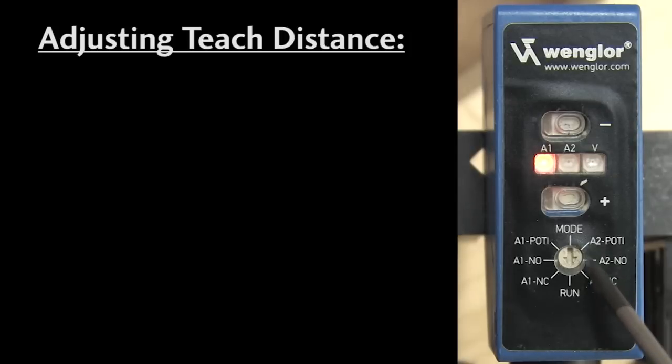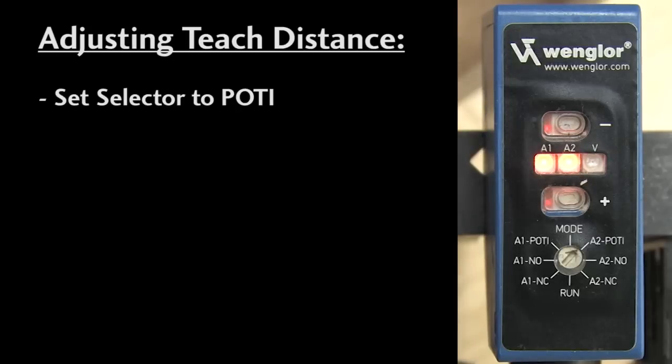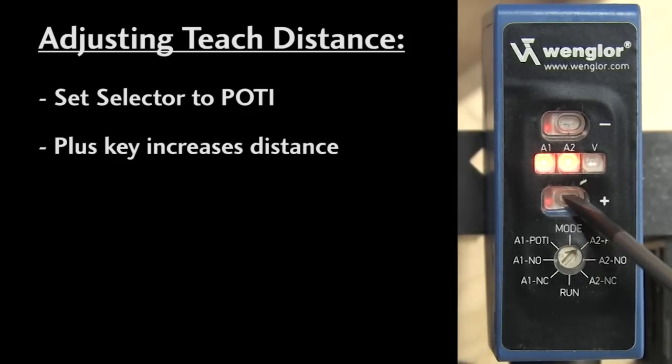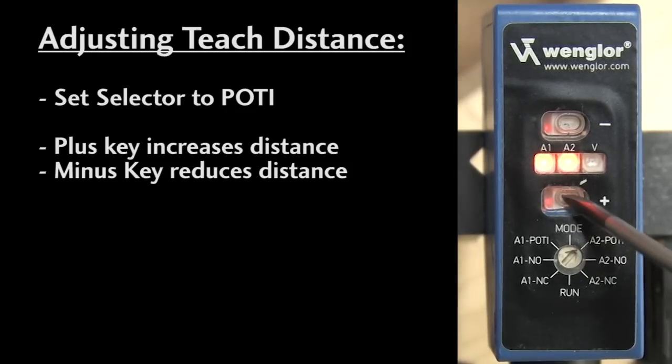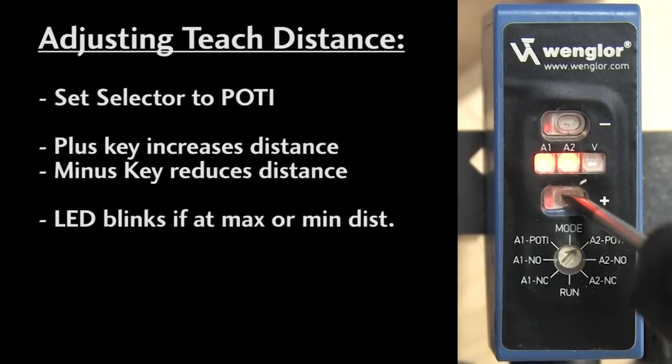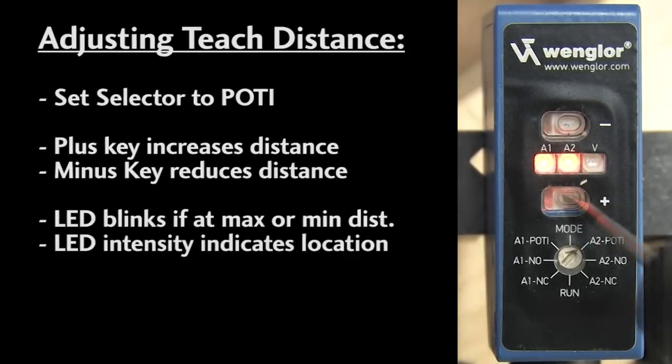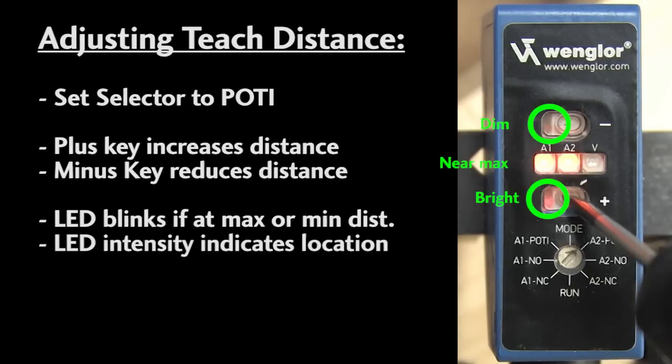Suppose you want to modify the detection point that you taught for an object in foreground or background mode. Just set the selector to the potentiometer setting for the output you want to adjust. That would be A2 in our case since that's the one that was set to foreground background mode. The plus key increases the distance, the minus key reduces the distance. If you hit the max or min distance, the corresponding LED will blink. And just like in window mode, the LED's brightness changes to indicate where you are in the range. I've found there's about 160 button presses to get from the max to the min. You can also just hold the button in and it will move the detection point. It took mine about 30 seconds to traverse the entire range from min to max.